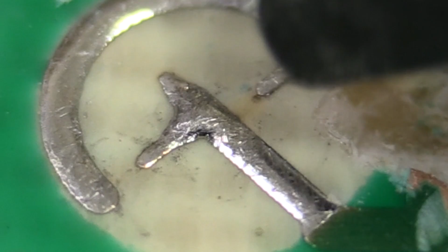When you have very sharp points, it can often be a one-shot deal like this, especially for high energy, reasonably high energy devices like this insulation resistance tester. If it arcs over like that and does it for a couple of seconds, then you can get some carbonization, and then, well, your board could be pretty much toast. So yeah, they could actually short out, so you've got to be careful.